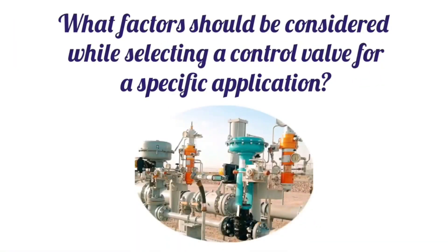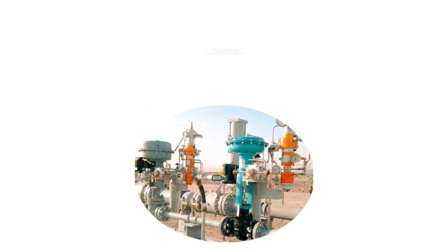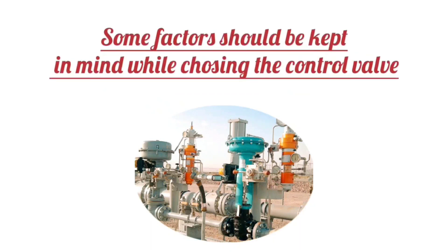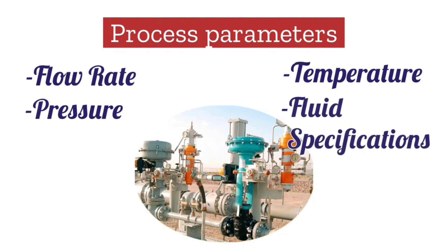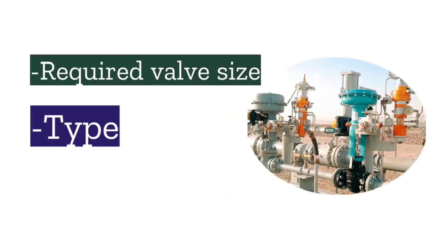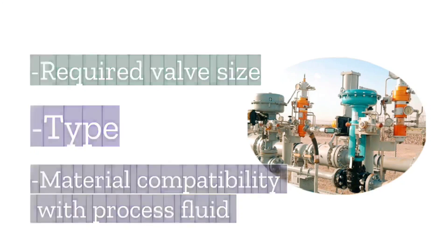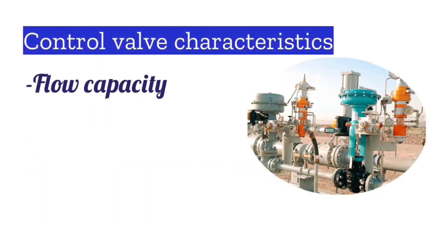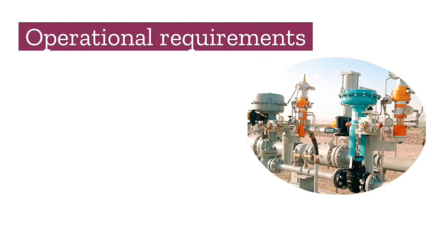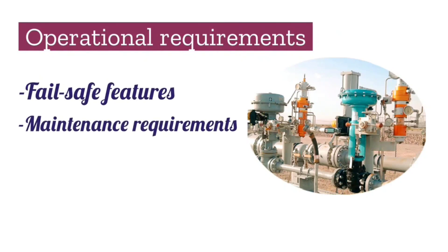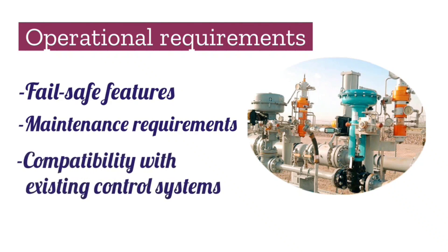What factors should be considered while selecting a control valve for a specific application? Some factors should be kept in mind while choosing the control valve, such as process parameters: flow rate, pressure, temperature, and fluid specifications. Apart from this, required valve size, its type, material compatibility with process fluid, and control valve characteristics like flow capacity, rangeability, and response time. Operational requirements are also taken care of, such as fail-safe features, maintenance requirements, and compatibility with existing control systems.